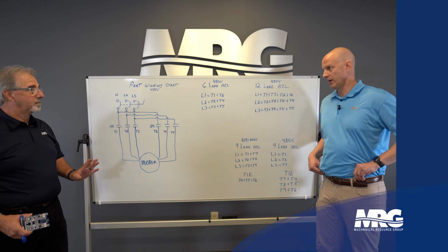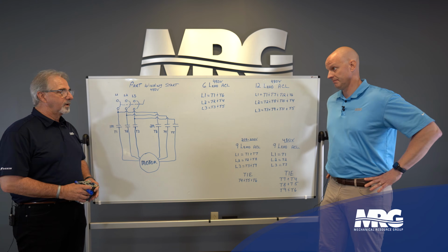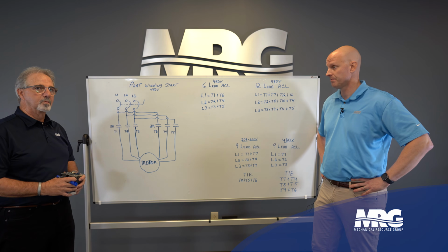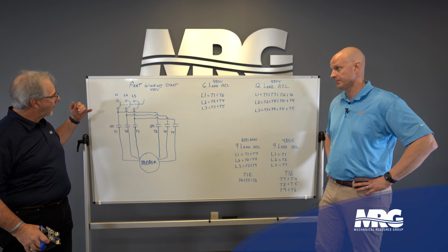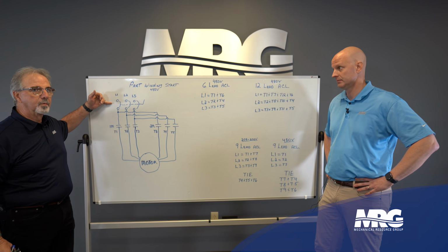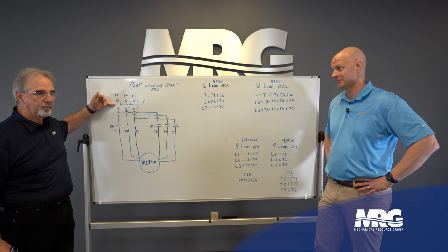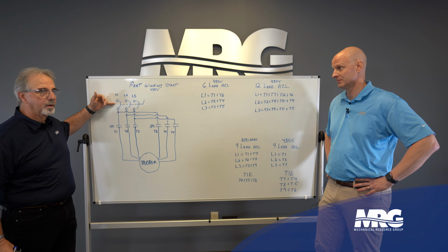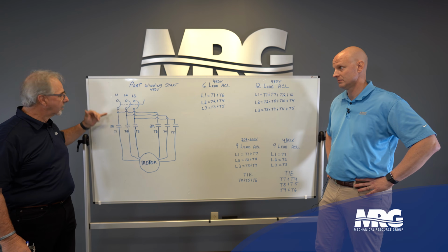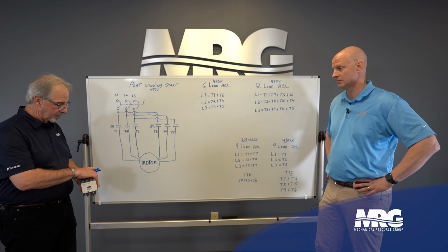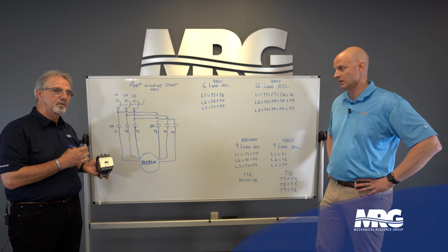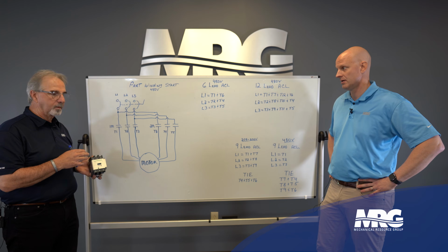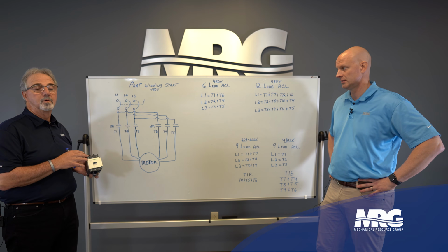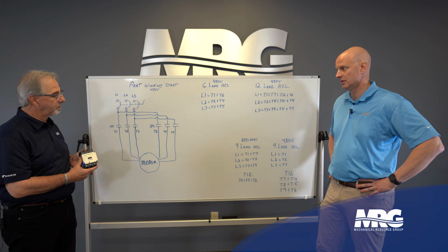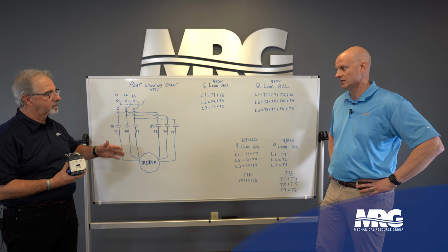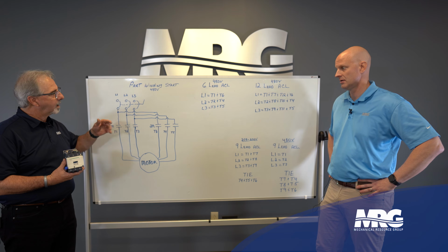We have a wiring diagram here, and I want to make sure that everybody understands some of the stuff that we're looking at. On the drawing itself, this would be your main circuit breaker. This is a three-phase ladder diagram. These are contactors, and if you've stood in front of these before, this is a 3-phase contactor. Now, in part winding start, we use 2 of these. I didn't do the control circuit; that's for another day.